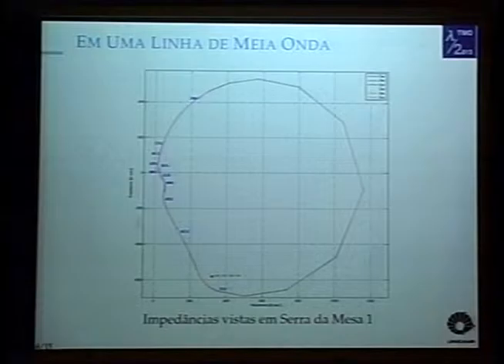The relay that is found on the substation has a maximum reach of 320 secondary ohms. So we would be talking about protecting only this segment that I'm showing you here now. And what would happen to the rest of the line? So here we have that the impedance without fault is here on this little square.